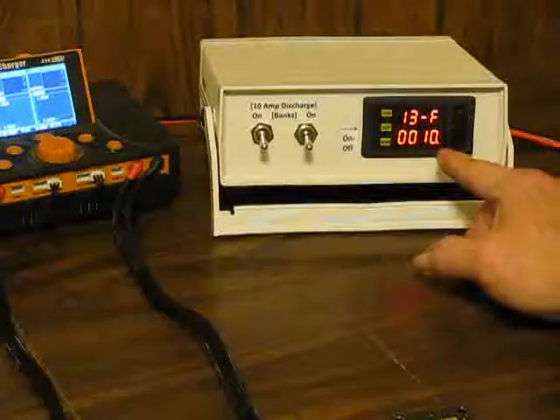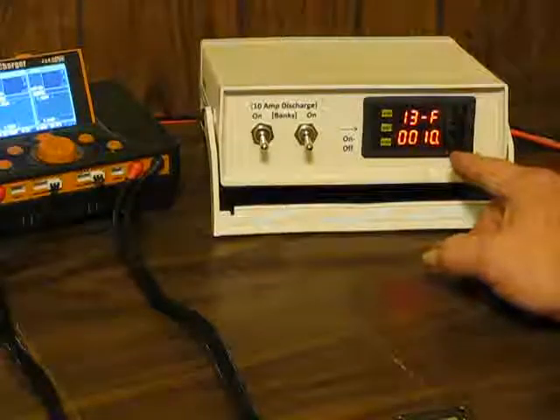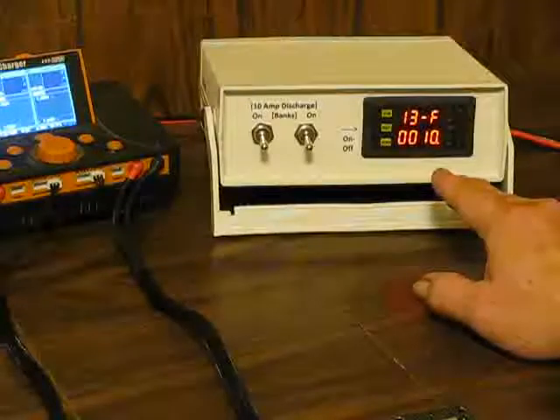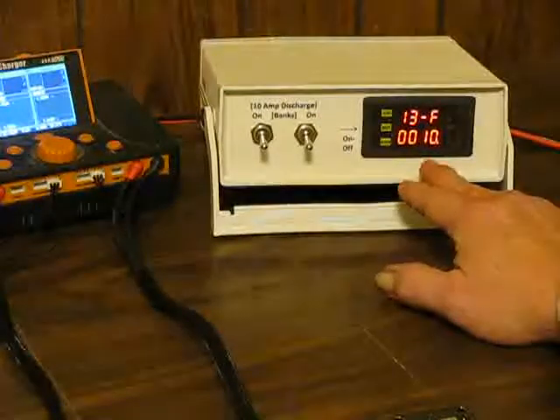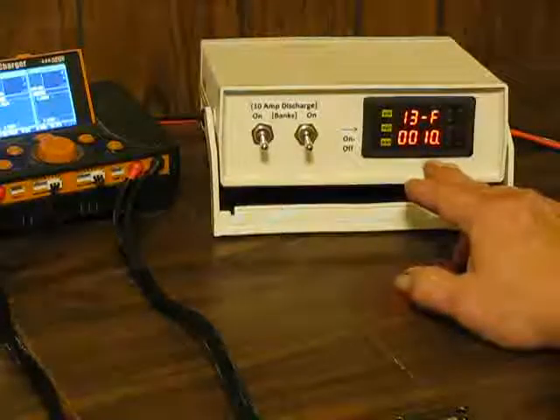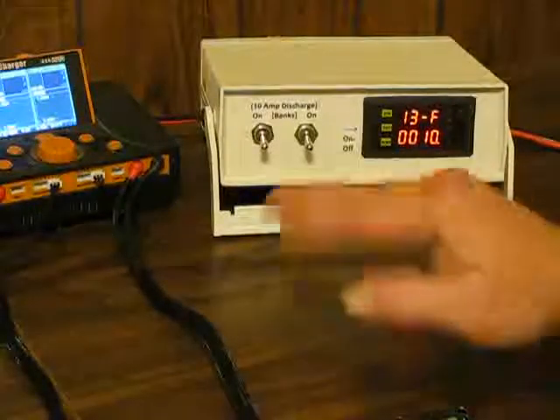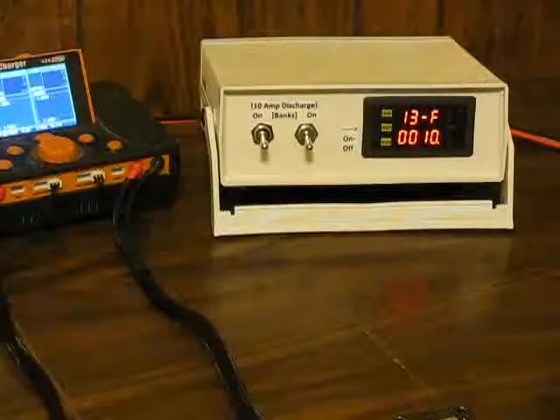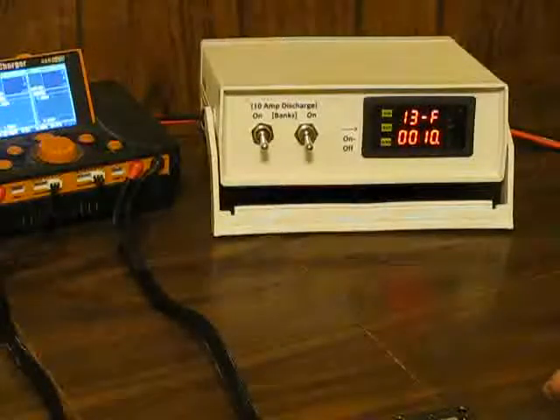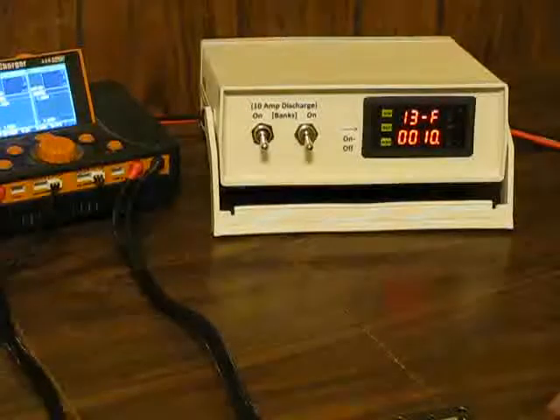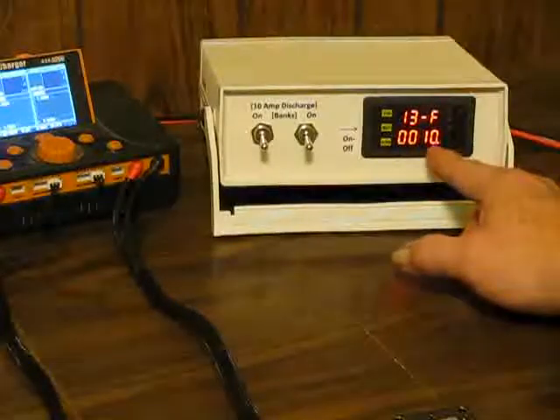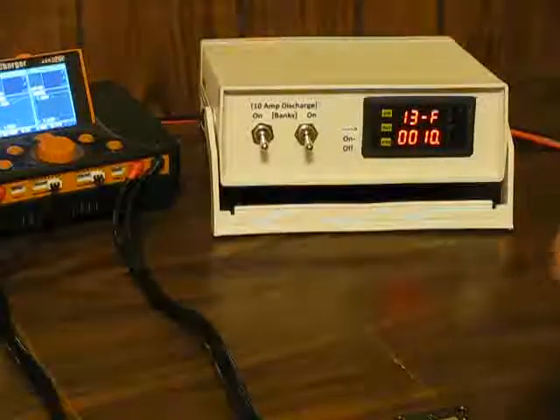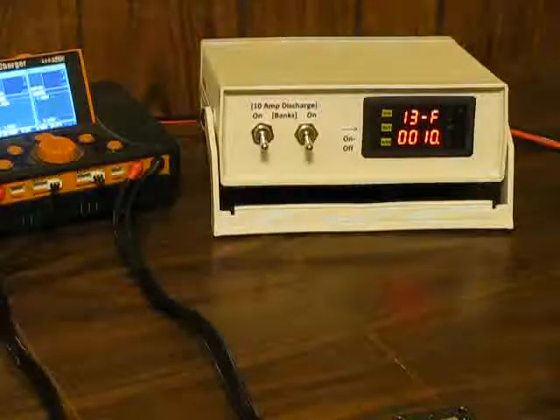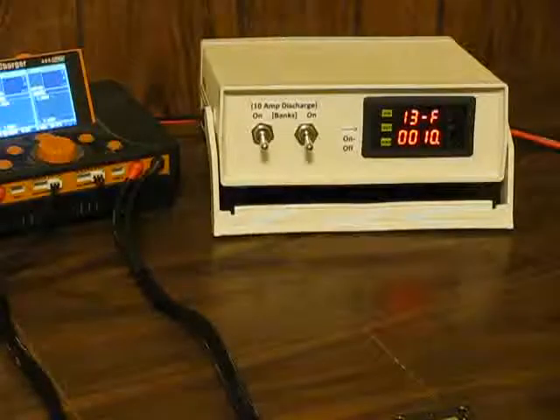13. And this is an older meter. There's 2 types of meters out there. And some of them will need to be set at 10, some will need to be set at 20. You can't tell the difference in the meters. Like I say, when I go through the calibration process before you get your unit, I'll have it set right. The instructions that come with the display, I include one of those with your unit, and those instructions will have the correct setting for this. It's on a table inside the instructions. It'll say what the default number is for that display. I will always have the correct one of them in with your unit, but it'll either be 10 or 20.